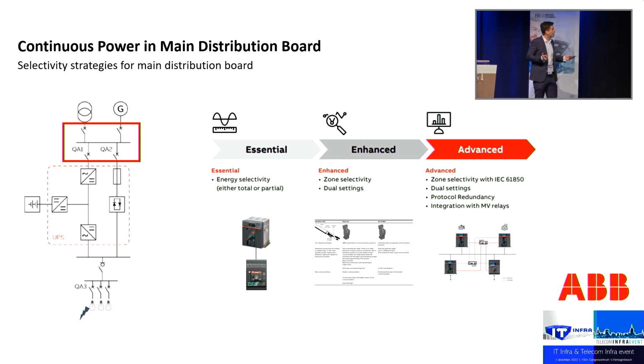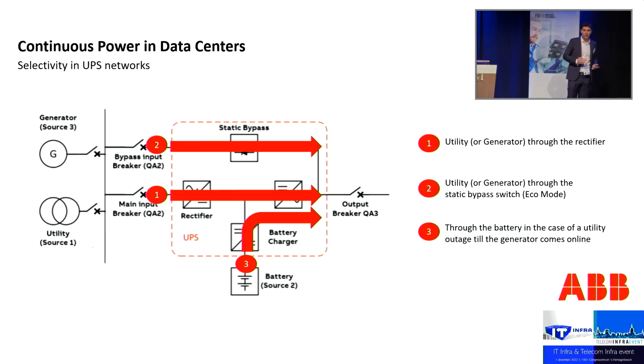So for example, I can also use in low voltage systems, and this is very interesting, the communication protocol called IEC 61850, which is, by the way, very common for medium voltage systems, and which is basically taken from medium voltage and implemented on the low voltage devices. So I'm further flexible to create even selectivity with the medium voltage devices. But let me jump into a more interesting topic, which is selectivity with the UPSs.